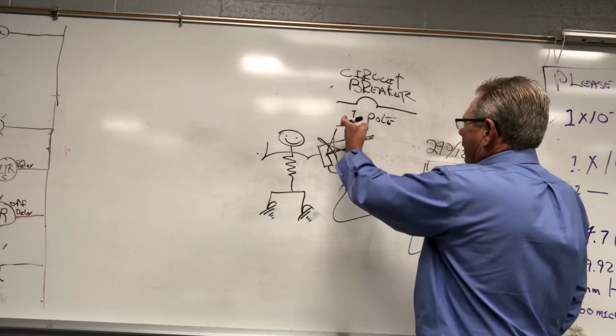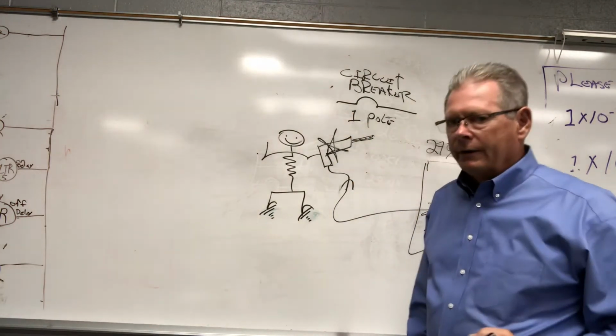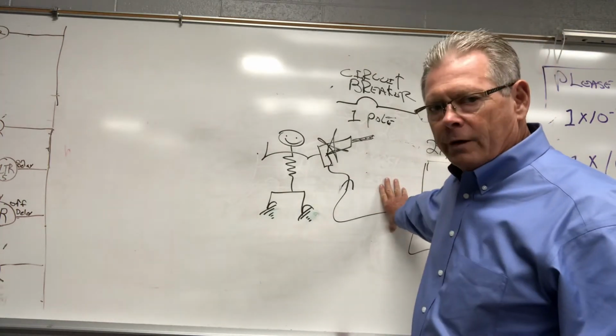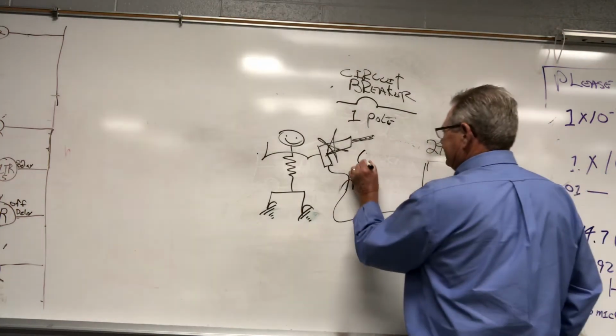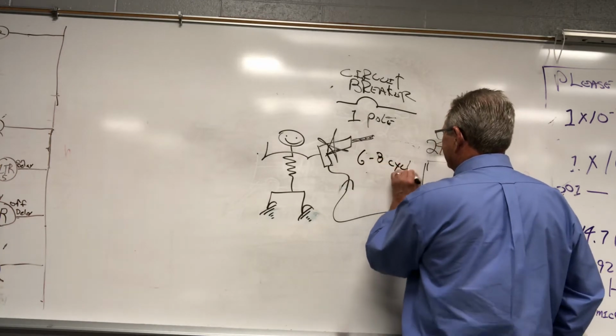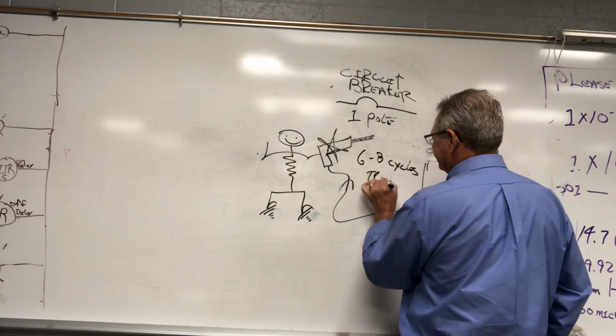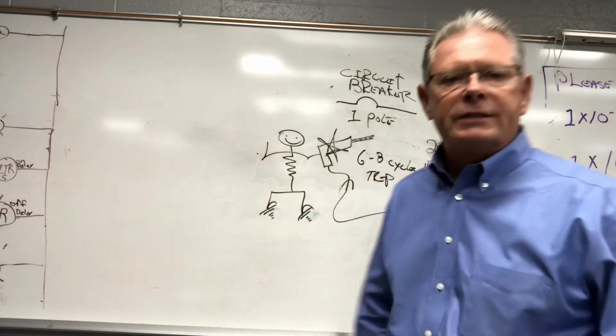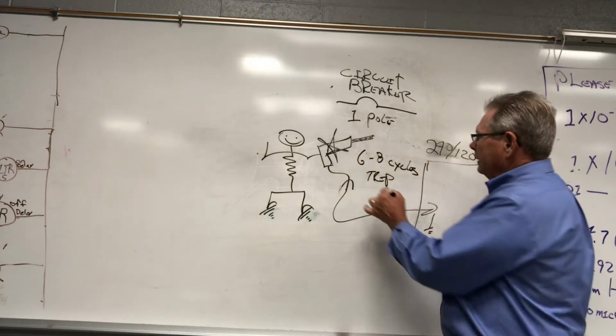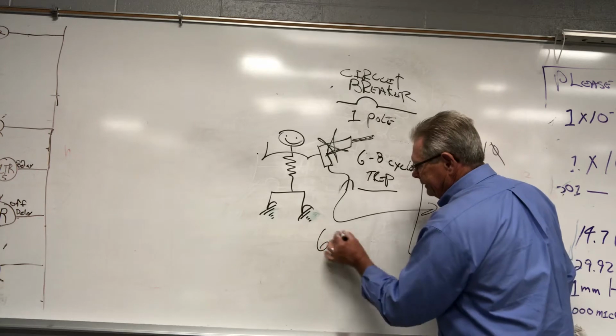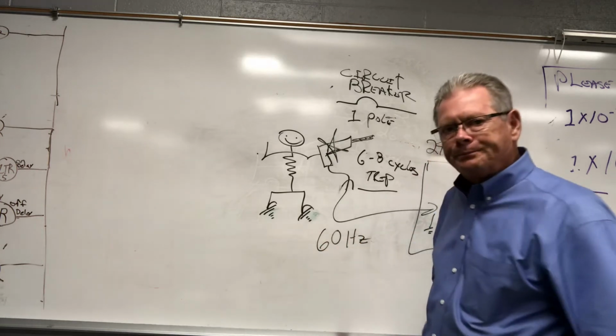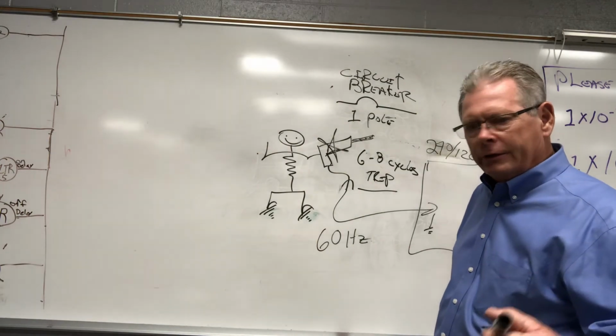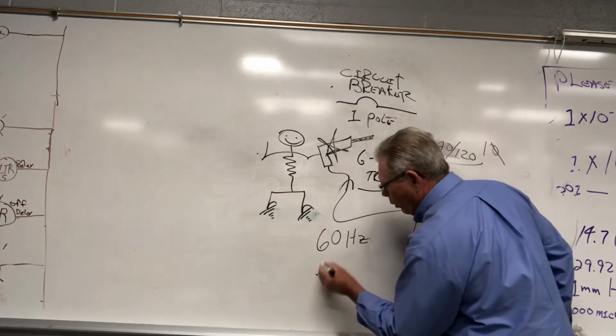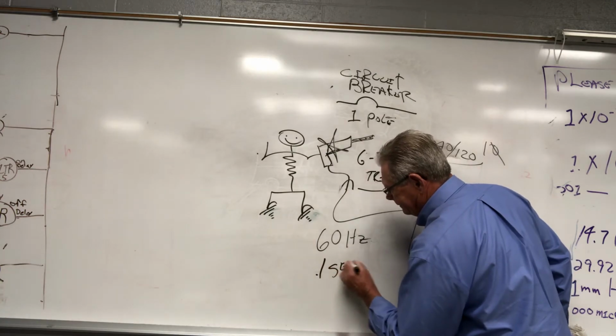Now, on your circuit breaker, if you get a direct short out on your circuit, it takes 6 to 8 cycles to trip. Okay? 6 to 8 cycles to trip. So we have 60 hertz, right? So on 60 hertz, 6 cycles is 0.1, or 1/10 of a second.